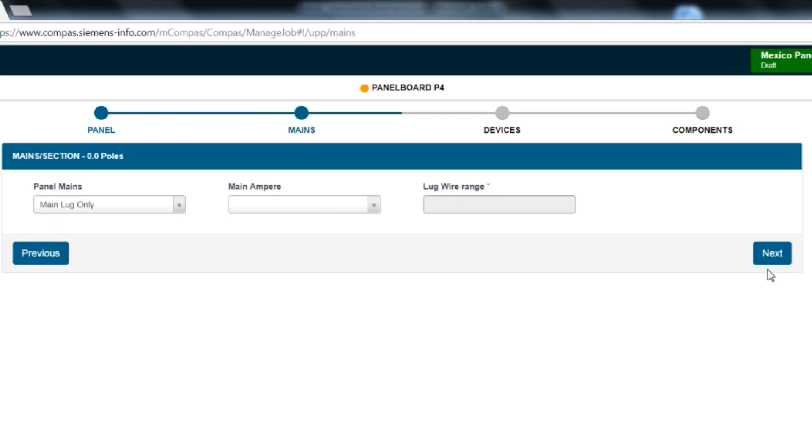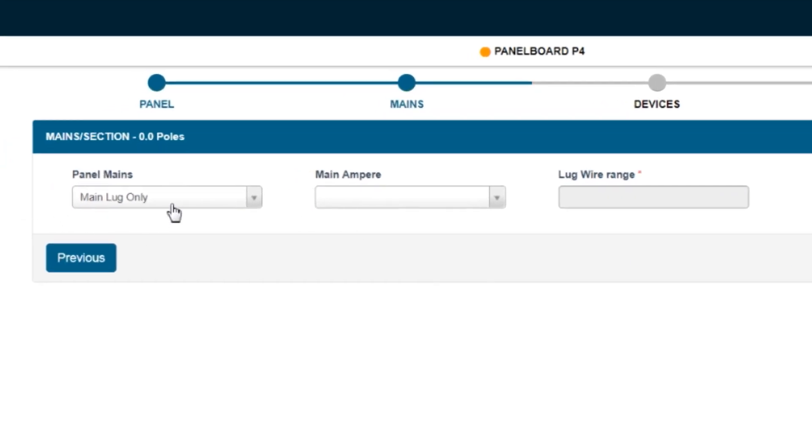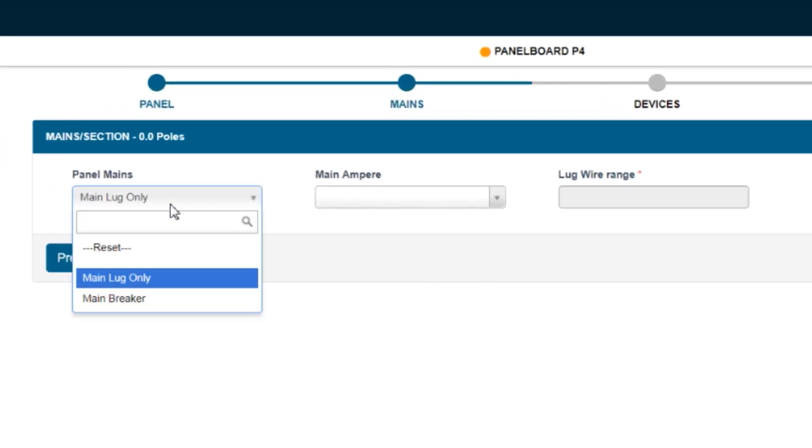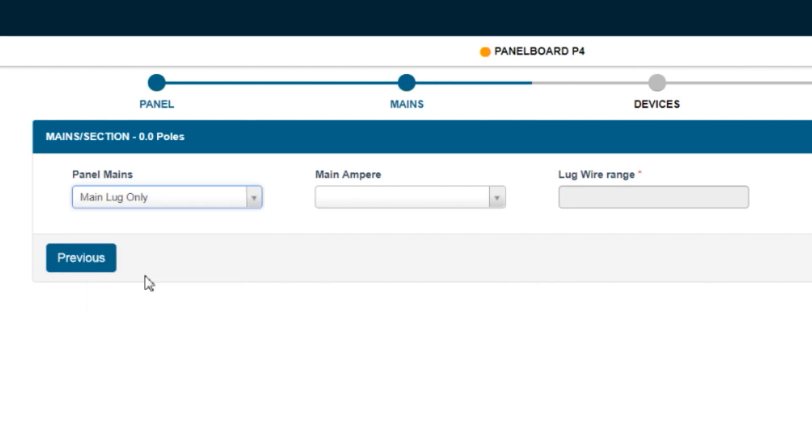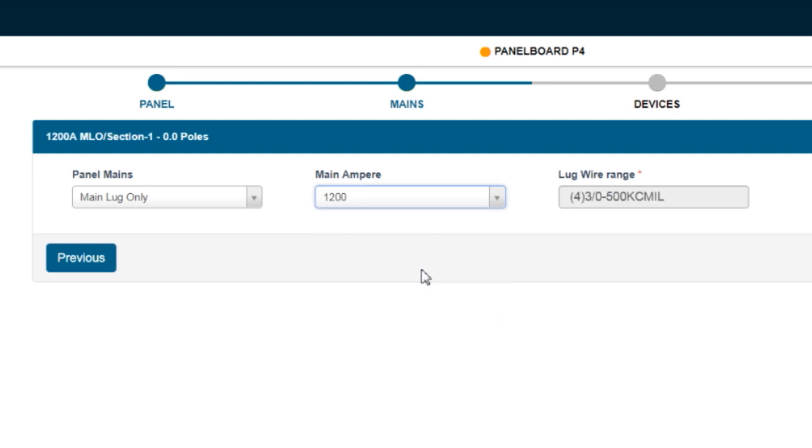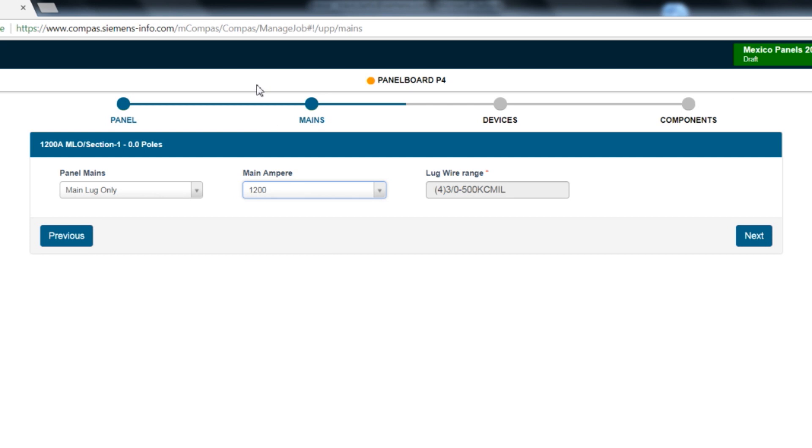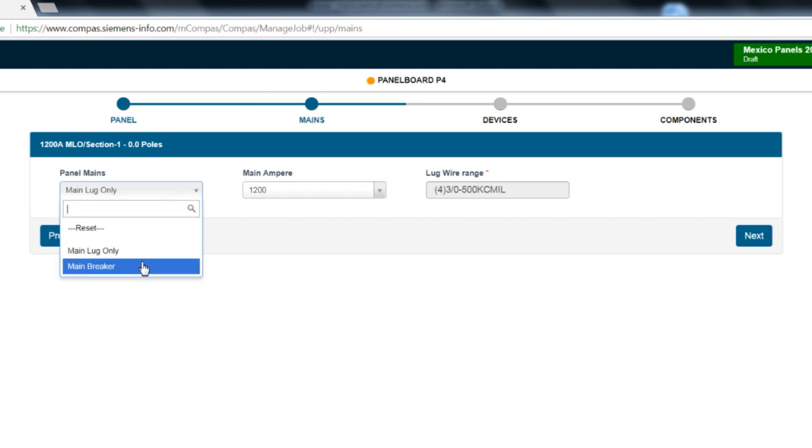The configuration screen has four options for the main breaker and two for the main lug. The first selection is main breaker or main lug. If you choose main lug, you will always use the 1200 amp main amperage selection that will drive the 1200 amp main lug kit. If you select main breaker, you will have more options in the following boxes.